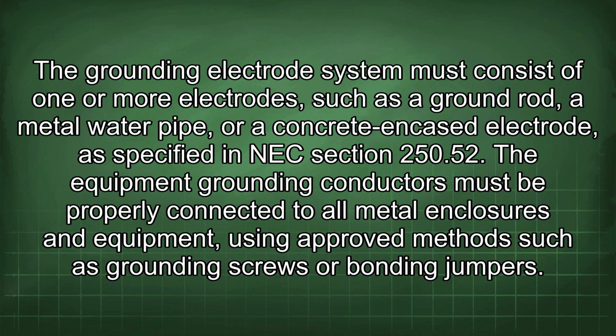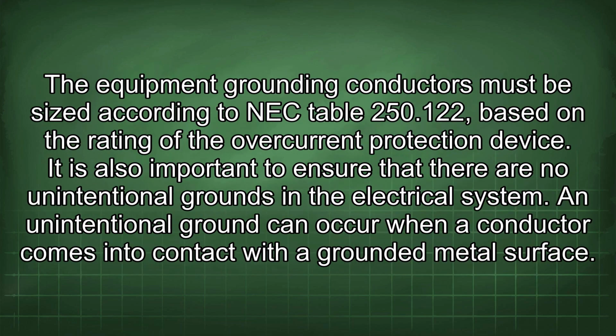The equipment grounding conductors must be properly connected to all metal enclosures and equipment, using approved methods such as grounding screws or bonding jumpers. The equipment grounding conductors must be sized according to NEC Table 250.122, based on the rating of the overcurrent protection device.